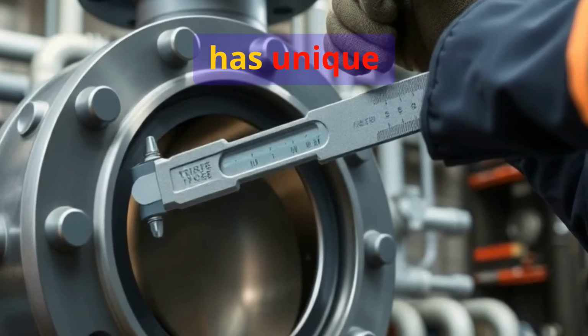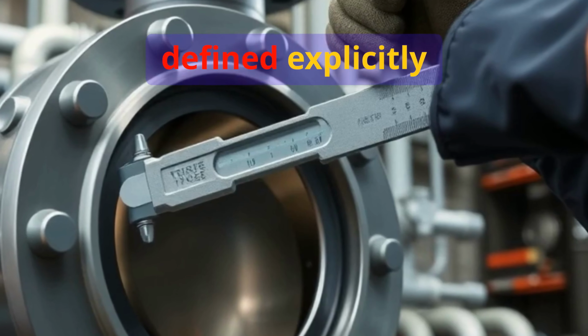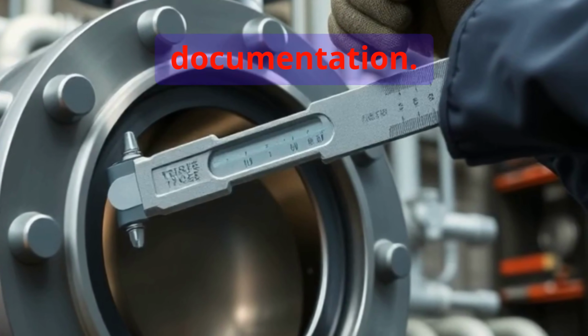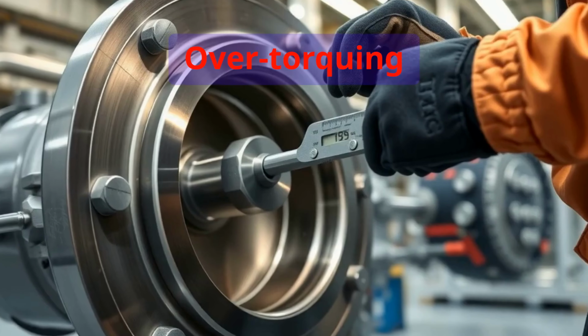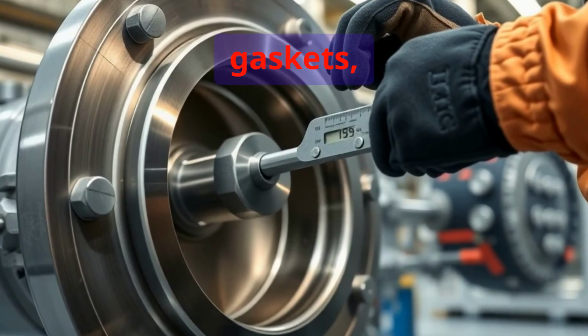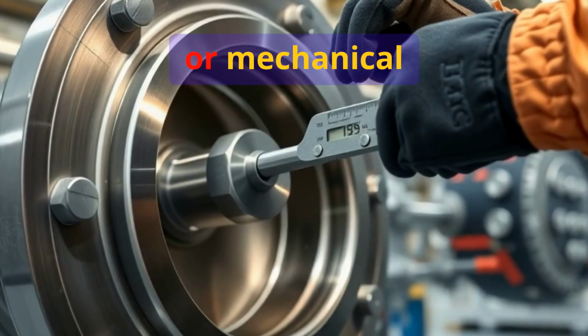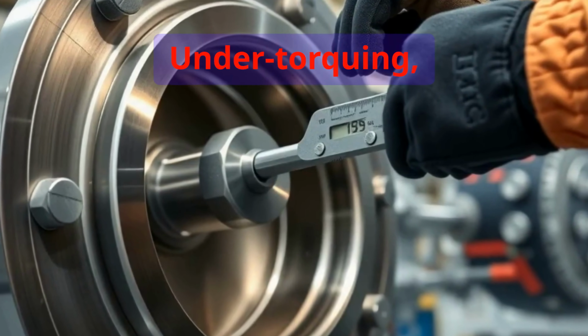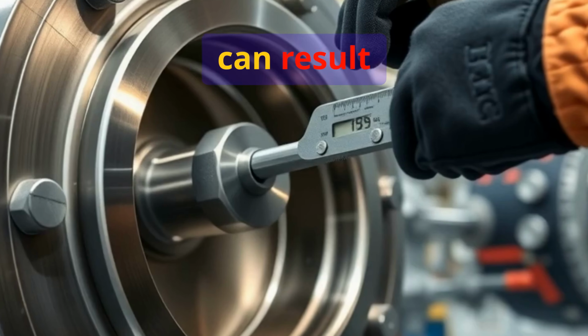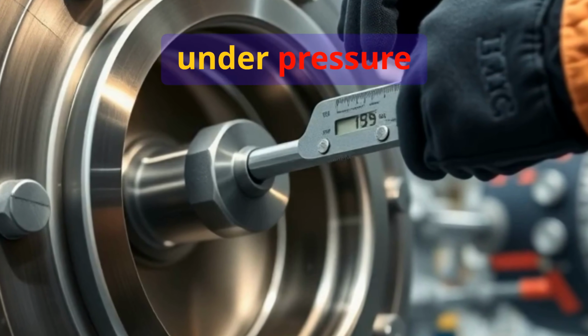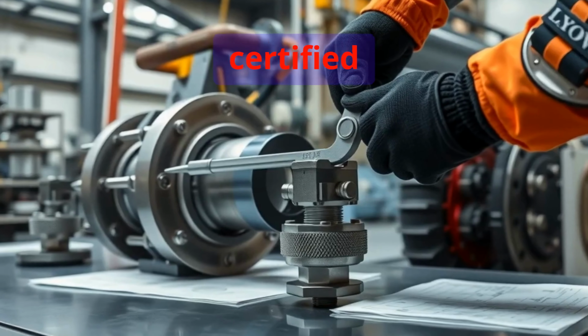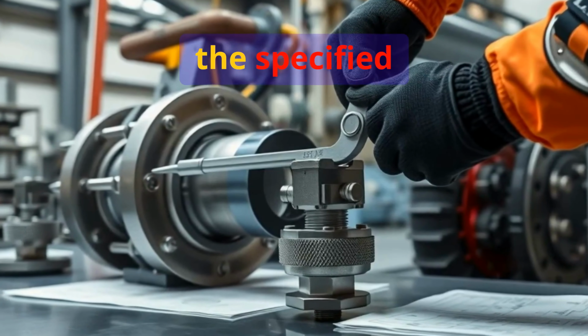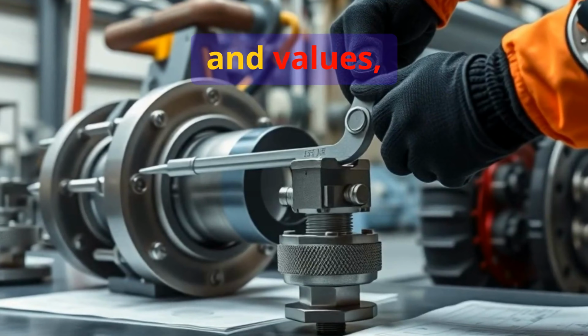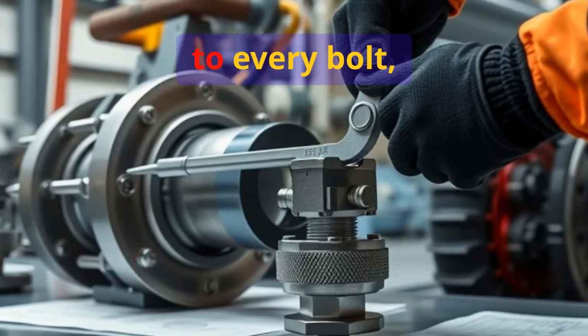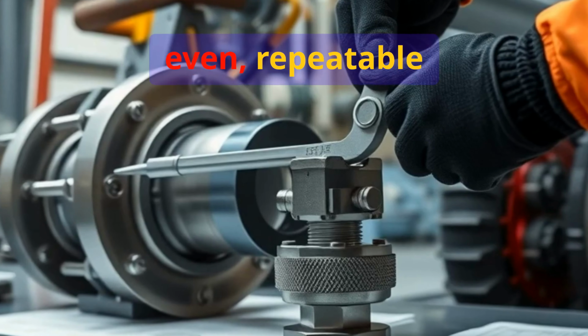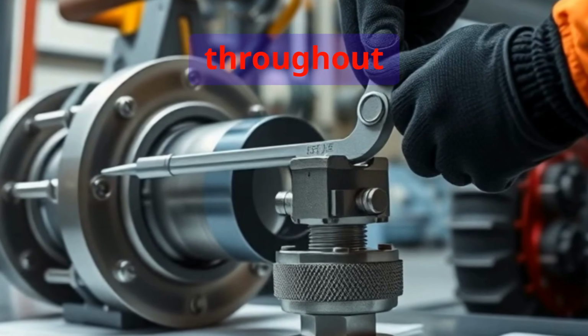Every valve has unique requirements for bolt tightening, defined explicitly in engineering documentation. Over-torquing can warp flanges, crush gaskets, or strip threads, leading to leaks or mechanical damage. Under-torquing, on the other hand, can result in gaps and loosening under pressure cycles. Utilizing certified torque wrenches and closely following the specified sequence and values, technicians document the torque applied to every bolt, guaranteeing even, repeatable sealing forces throughout the system.